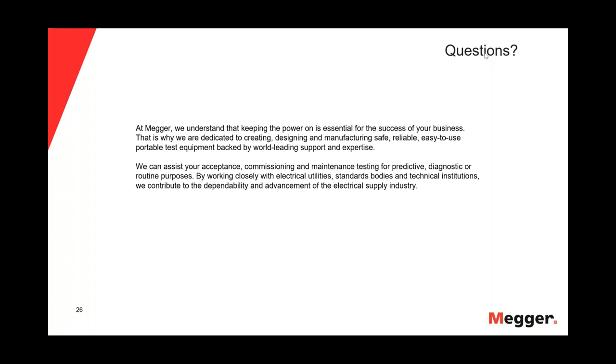Thank you, Javier. Additionally, is a DC HIPOT test a prerequisite for a VLF test? No. Indeed, for XLPE and EPR cables, the DC HIPOT is no longer recommended. We only recommend using the DC HIPOT on paper insulated cables, okay? But for sure, if you are dealing with solid dielectric cables, EPR or XLPE, the only thing you need is the VLF, and indeed the DC HIPOT is no longer recommended.